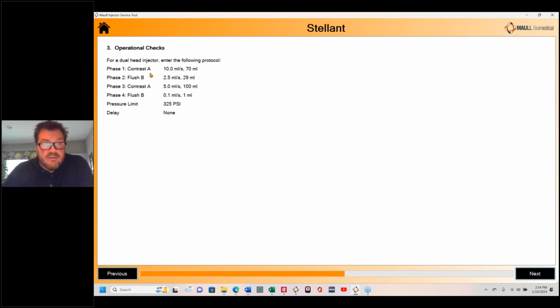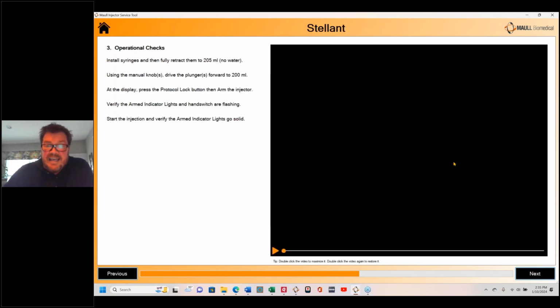So we're telling the operators, enter this protocol. Phase 1, 2, 3, 4. So this is a 4-phase injection. I know that might not mean anything to some of you, but first phase is going to be contrast. Then we're going to shoot some flush solution. Then we're going to go back to contrast. And then this is phase, and we're going to shoot in each phase. Remember these numbers: 10, 70, 2.5, 29, and so forth. I'm going to set a pressure limit of 325 psi. Pressure limit is sort of a drawn out explanation, so I'm going to skip over that. If you want to learn about pressure limiting, go to Introduction to Contrast Injectors, no delay.